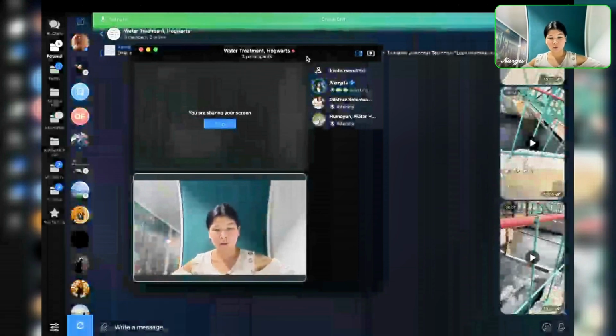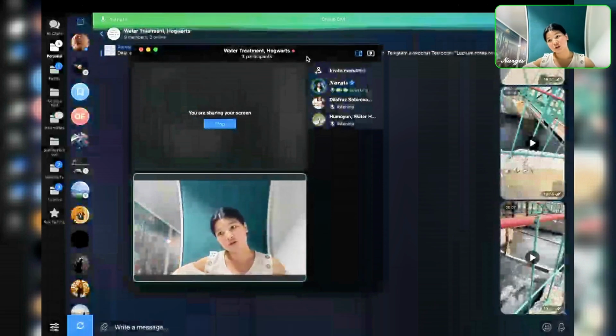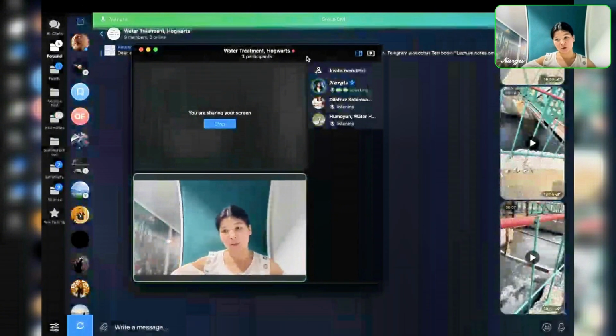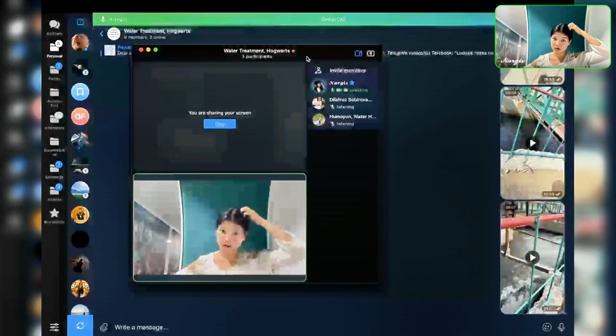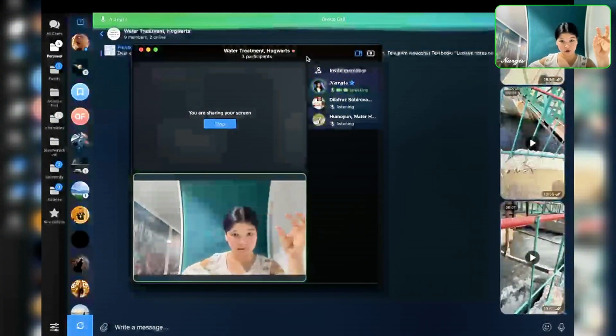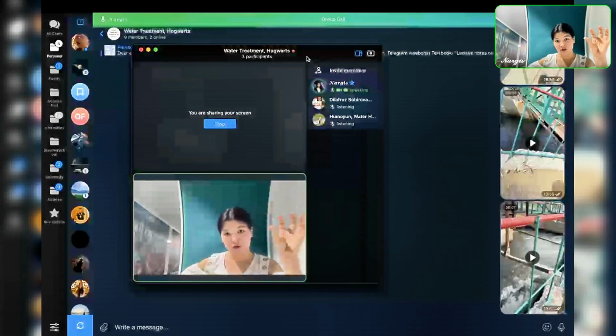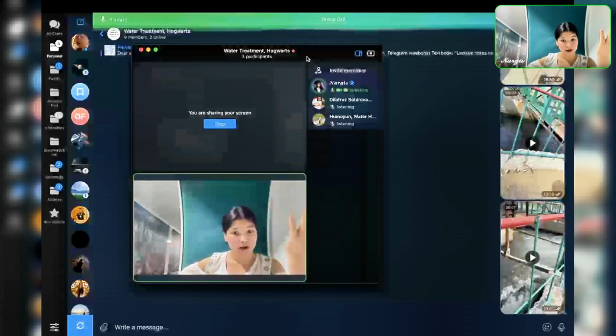I don't really know how it's done in other countries and whether they use hypochlorite at all. But here in Tashkent, they just have these tubes where hypochlorite is run, and they have a control overflow, so they can send a lot or a small amount, and based on the E. coli concentration, they change it. So in this way, they do this process.